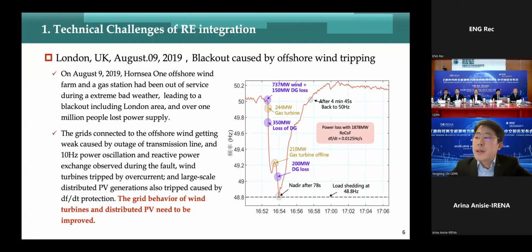The grid was getting weak because of the outage of a transmission line. A 10 Hz power oscillation and wind turbine tripping by overcurrent were observed during the fault. Also, large-scale distributed PV generation tripped because of the rate of change of frequency, or ROCOF, protection. The setting is too small.